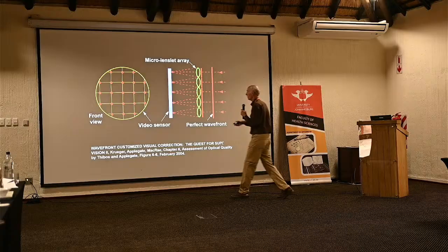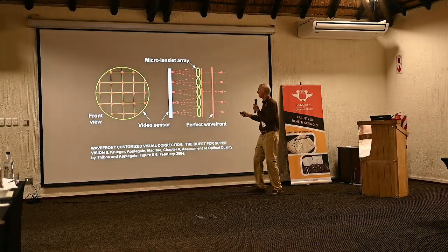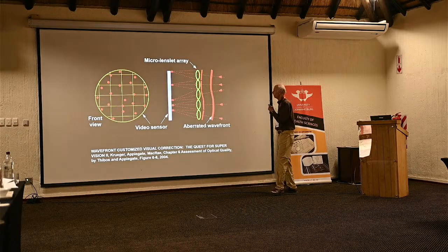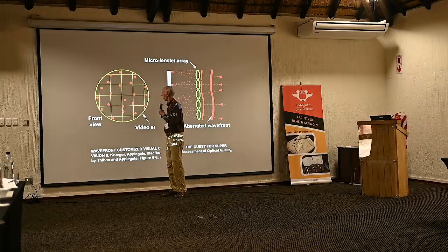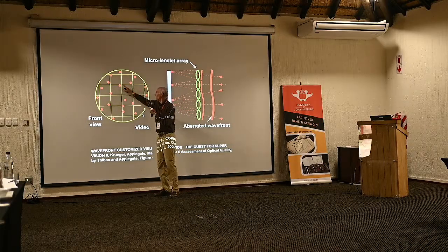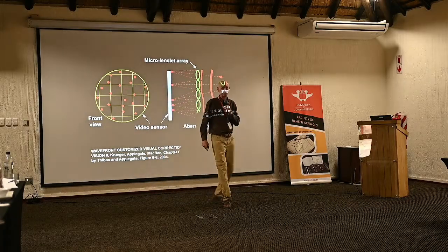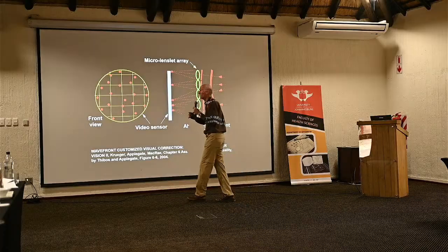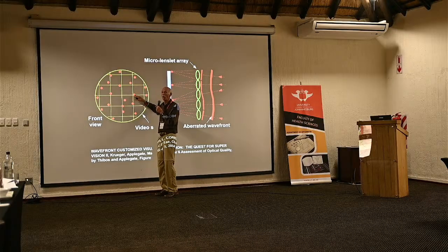The ideal location of all these points, of course, is a perfect grid. That's part of the calibration procedure of the instrument. And then in the end, you have the spots wherever they went. Interesting image. Notice there is no spot here. That square doesn't have a spot. Why not? Depends on how the instrument's designed. It's possible that the spot that was supposed to be in that square moved so far, it moved out of its box and landed up over there.